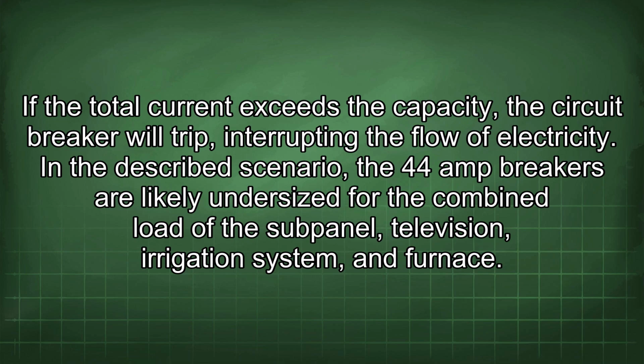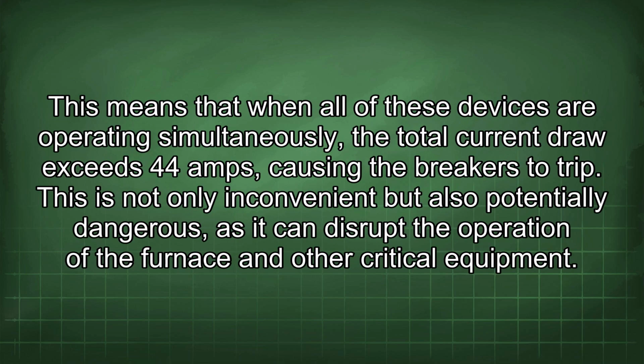In the described scenario, the 44 amp breakers are likely undersized for the combined load of the subpanel, television, irrigation system, and furnace. This means that when all of these devices are operating simultaneously, the total current draw exceeds 44 amps, causing the breakers to trip. This is not only inconvenient but also potentially dangerous, as it can disrupt the operation of the furnace and other critical equipment.